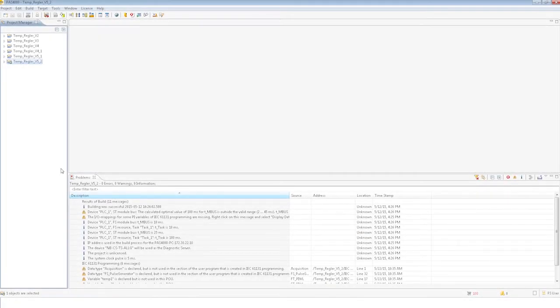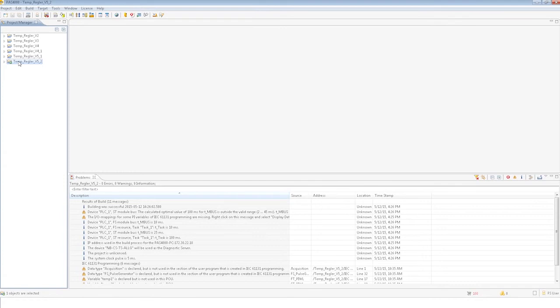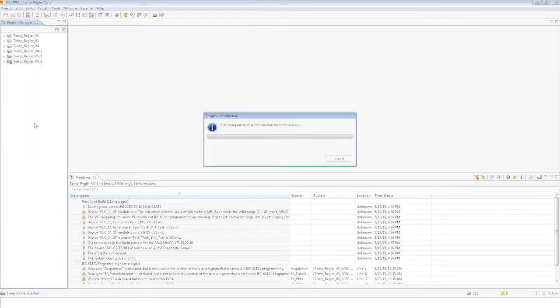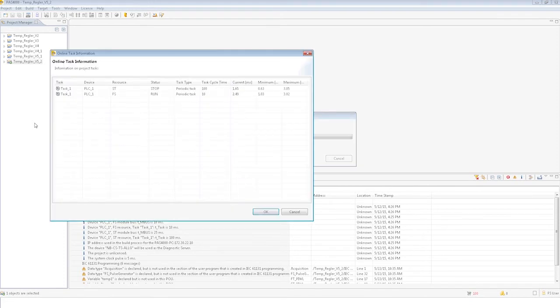Now let me show you a function that you can use to view the current load of the PSS online. This is available under the Project Context menu under 'Show Online Task Information.' You will see an overview of the tasks and the actual cycle times that are needed. Please note that you shouldn't fully utilize the configured cycle time.